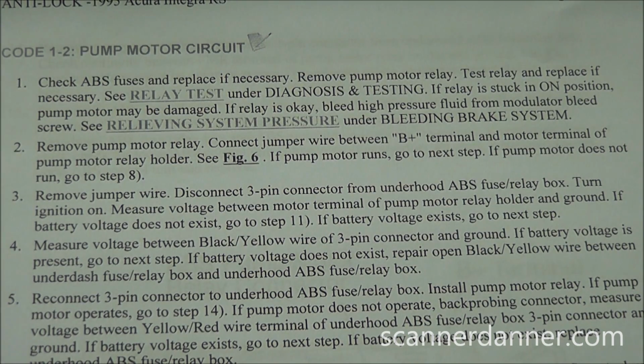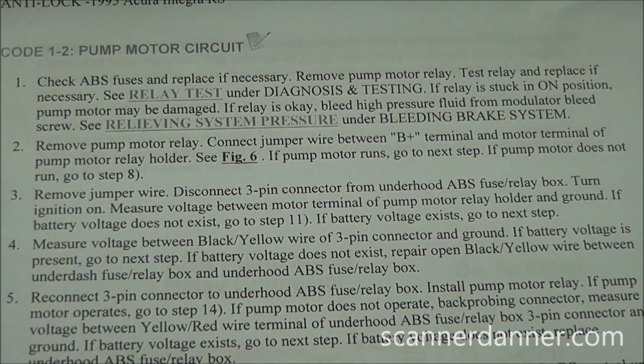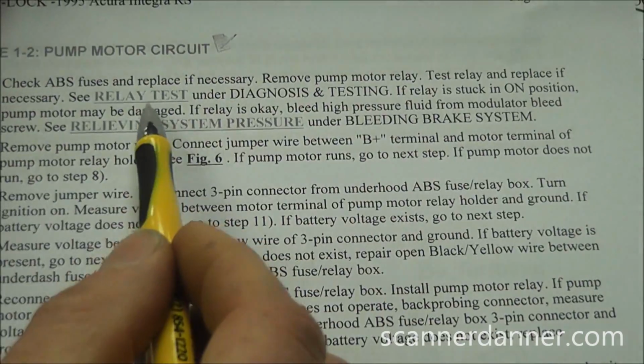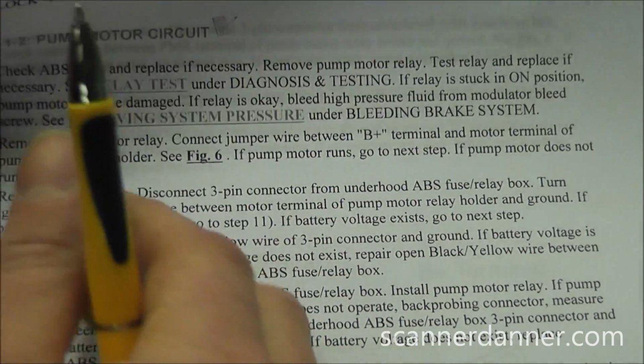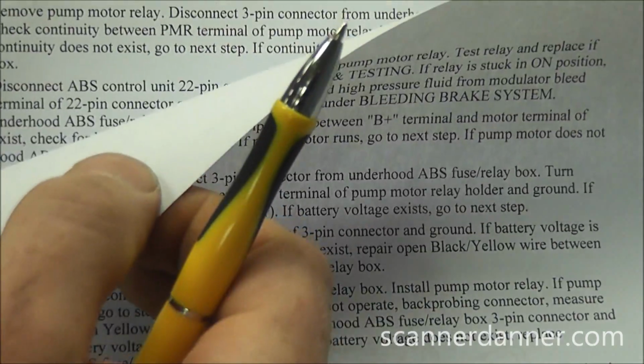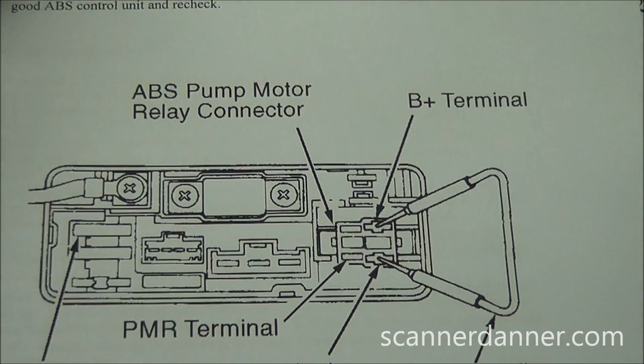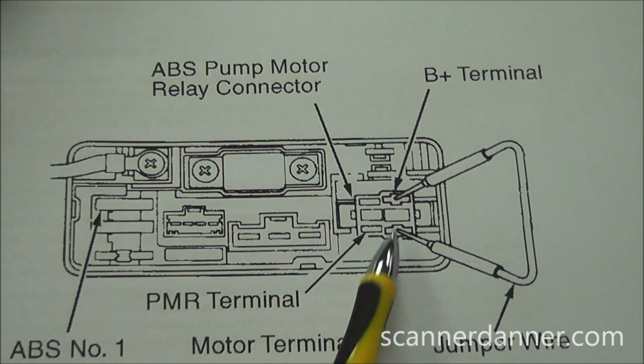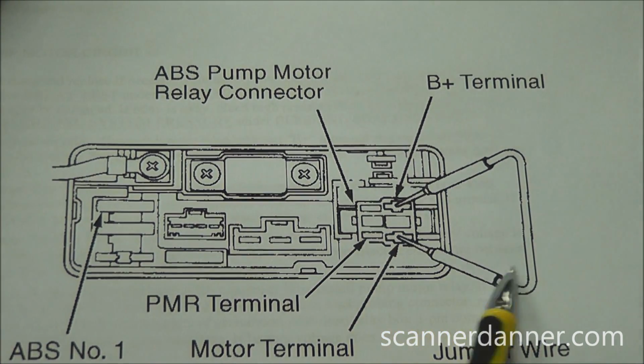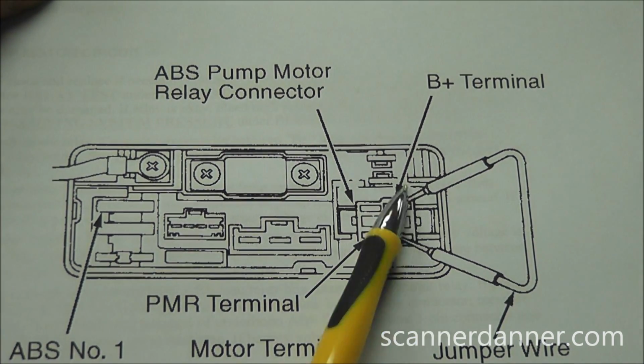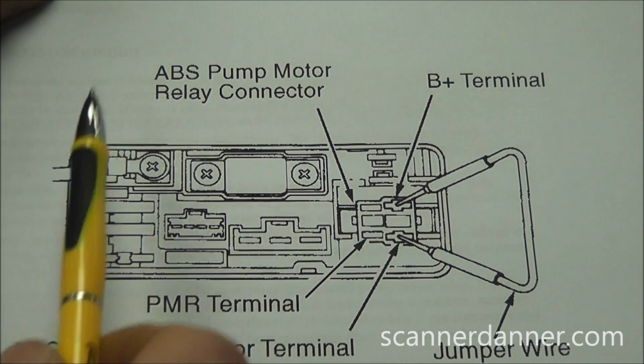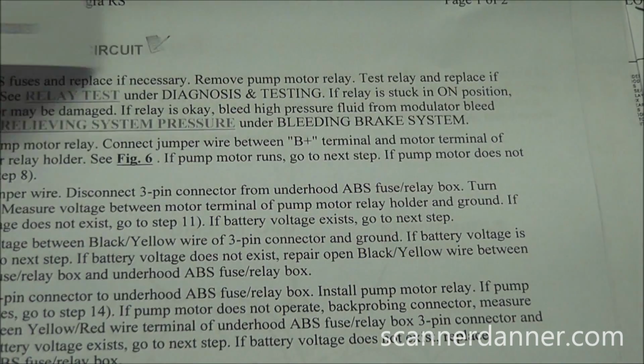So right away we're doing a relay test. And what they have us doing for the relay is basically jumping it, bypassing it. I printed that. You see this is kind of a different color here. This relay test is basically, they want you to remove the relay, install a jumper wire on the load side contacts, and then check your motor for power. That's basically what you're doing.